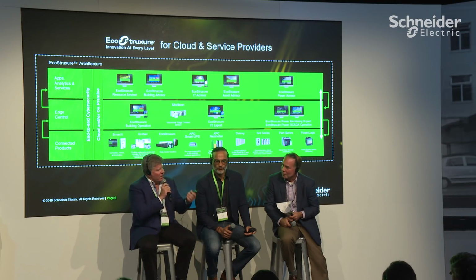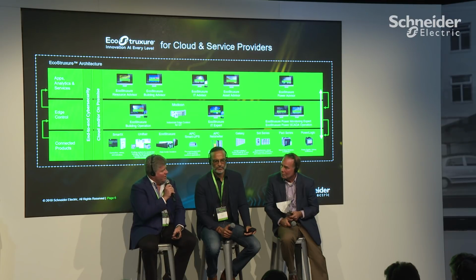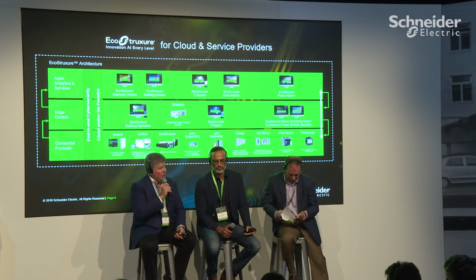Now, having an autonomous control system that constantly uses reinforcement learning, gaining insights from the billions of data points we've gathered over the years on our data center operations, lets us predict how best to set up the data center for those weather and IT related variables—looking at everything from differential air pressures to water flows, outside air temperature, and wet bulb. Add them all up, and there's about 19 that are impactful to reducing your PUE, and the numbers we've achieved are truly dramatic.